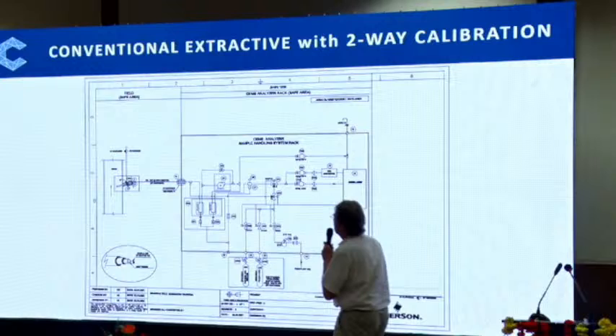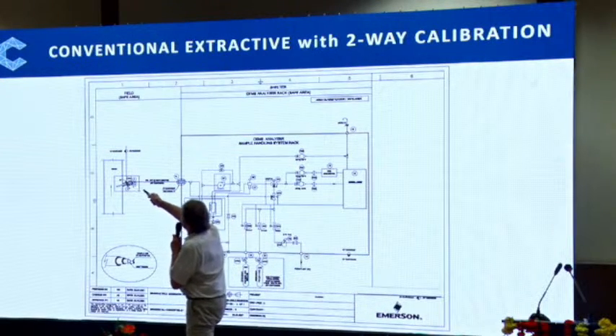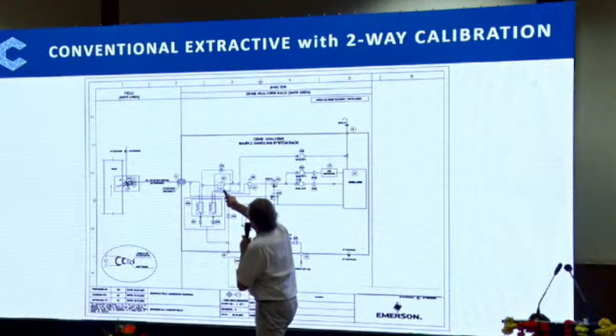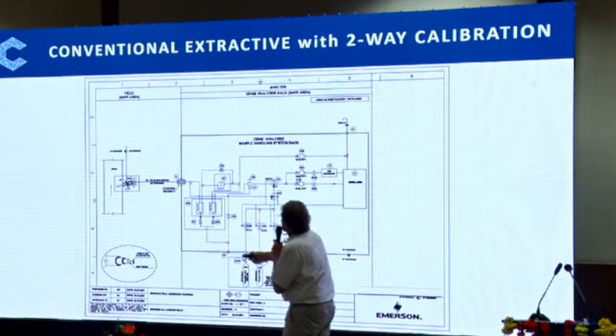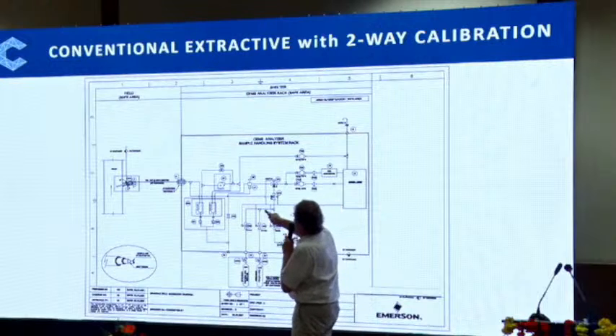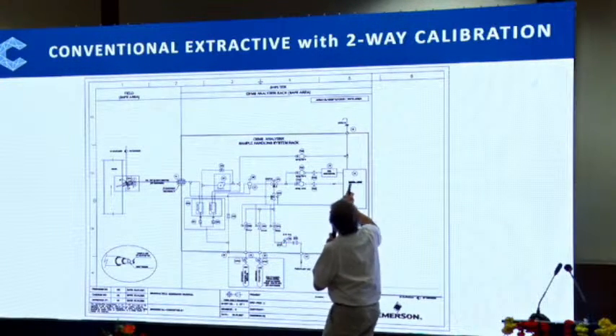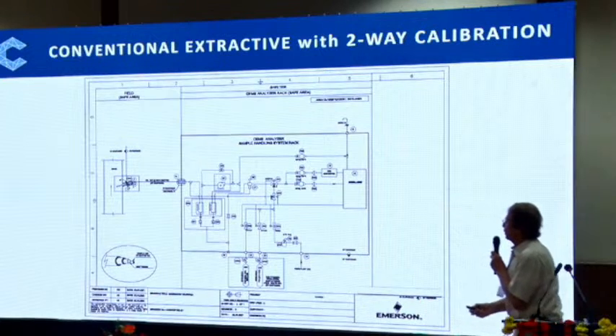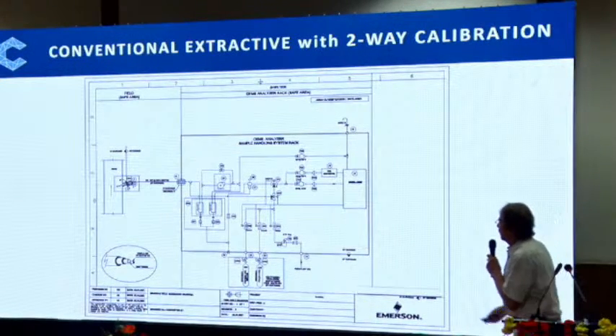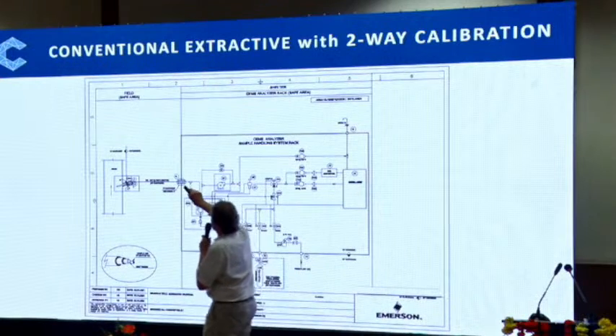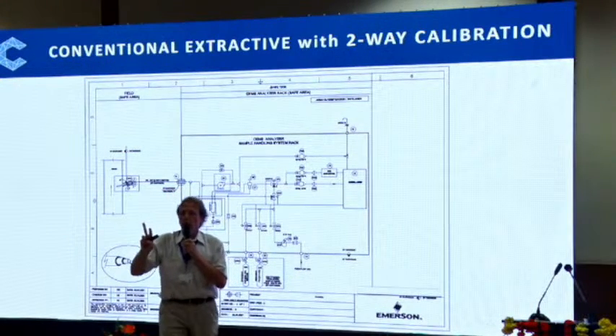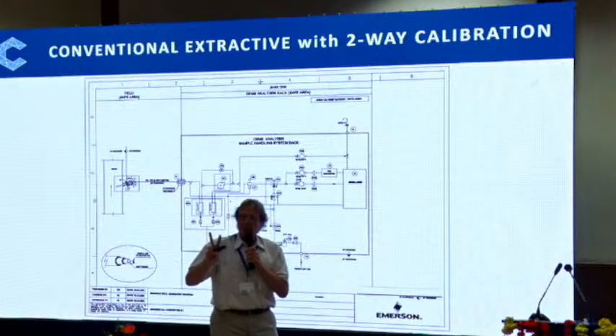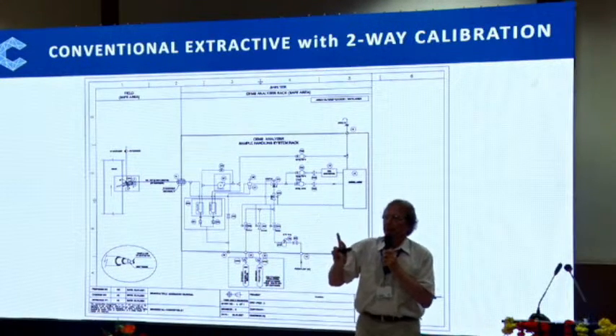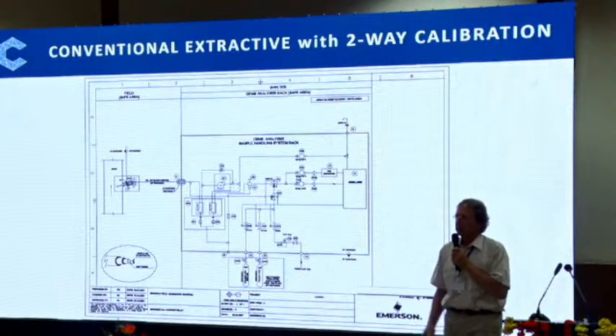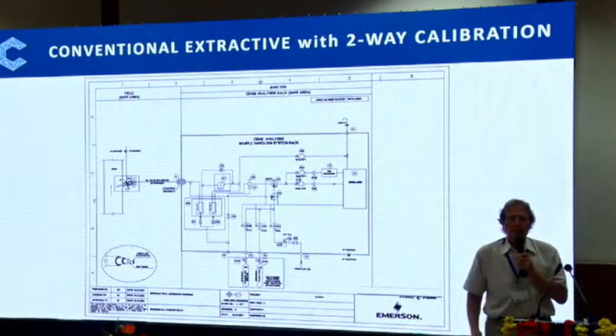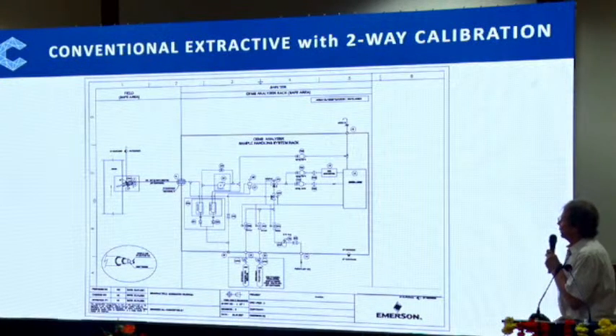Typical system looks very much the same. Sample probe, heated umbilical, we've seen that before. In this case, it's a European type. Sample gas cooler, going the calibration gas either there or to the analyzers, and all the valves, etc., what is required. Calibration gas typically goes through the umbilical, so that's umbilicals with two lines, two tubes. One is heated for sample, and the other one is unheated for the calibration gas. So I get my calibration gas up to the stack and my heated sample gas down to the analyzers.